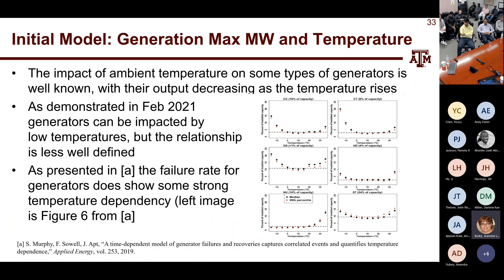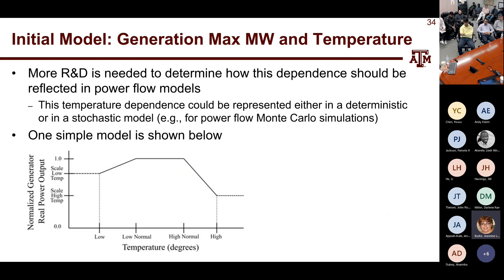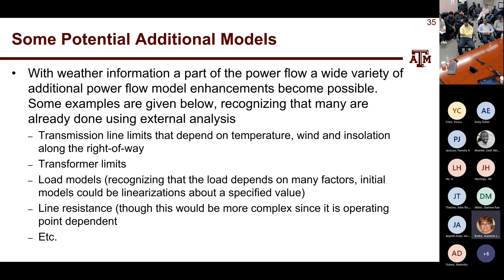We're also working on models for generators and temperature. For thermal units it's not a direct correlation — it's more probabilistic. Generators are more likely to fail at both high and low temperatures. So we're setting up probabilistic models to play different conditions and ask what would happen under 1949 weather or other scenarios. Another model we're working on heavily, with utilities, is transmission line limits — they depend on temperature, wind, and insolation along the right-of-way. The simplest approach is making them temperature-dependent.